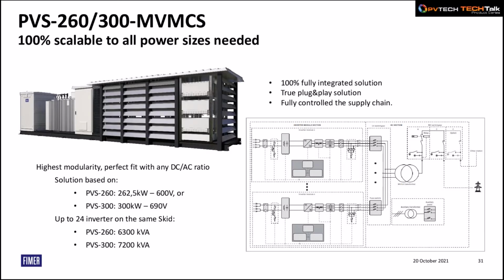Okay, just to dive into the product details, the system is a perfect fit with any DC-AC ratios because we are able to offer single building blocks of PVS 260, which is a 262.5 kilowatt power module with 600 volts output, as well as a 300 kilowatt module with 690 volts output. So we have the ability to replace all the conventional monolithic central inverters. Bundling together up to 24 of these modules, we are able to cover up to 6.3 megavolt ampere with the PVS 260 and as high as 7.2 megavolt ampere with the PVS 300.